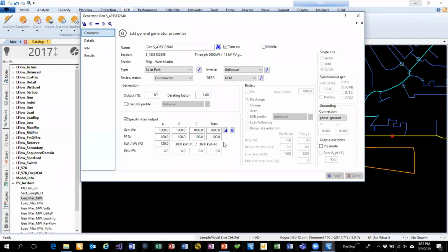What we're saying is, what is the rating of the inverter? We have the capability of the solar panels, and that's these numbers up here. So this generator can output 3 megawatts. The question is how much AC power can we put out of this? In this example, this is set to 120%. We've simplified this label, 120%, and then we've put in this piece of text here. So this is saying we have a 3 megawatt DC rating, and a 3.6 megawatt AC rating. For a lot of you digging into this, that reflects how much VAR capacity you have. So this thing could be running full bore, full output at 100% irradiance, generating 3 megawatts, and I still have VAR capability, so I can swing the power factor back and forth.